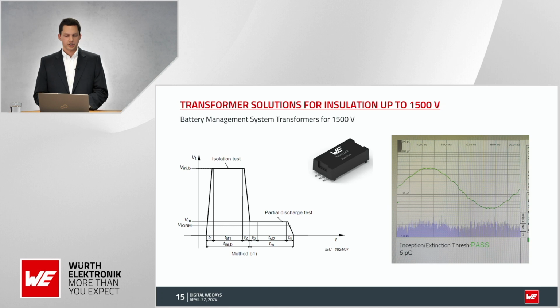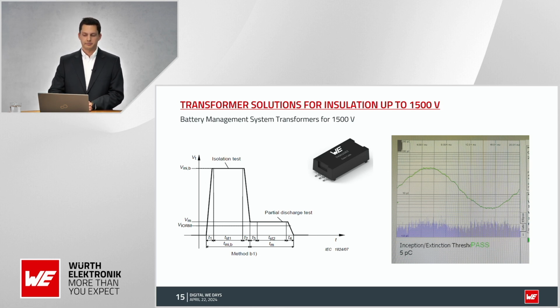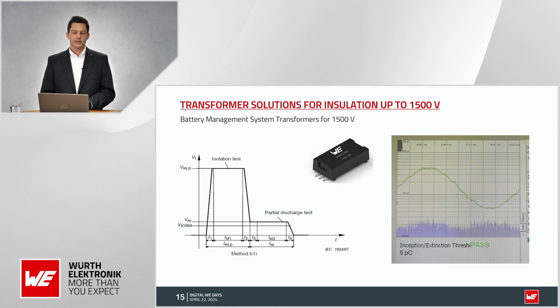Also, even if these discharges have small energy, the thermal energies due to the discharges can cause aging, deformation, and tear of the isolation material. Partial discharge is a failure process that starts small, always gets worse, and leads to flashovers. Therefore, fixed isolation in which partial discharges occur during operation is not permitted in the long term. This test is passed if the quantity of partial discharges is below a limit value of 10 picocoulomb. The test procedure is standardized, so as you can see in the picture on the right side, even a stricter test with 5 picocoulomb is passed.